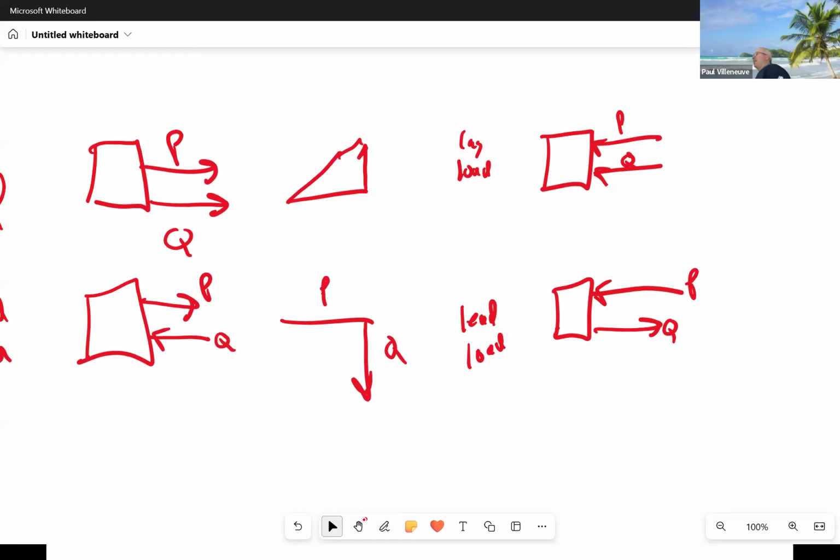So this adds a lot of complication because when we think of load, we think we're always pulling stuff in, but not Q. Q can be in or out. Many, many loads can be providing Q if they're capacitive, right? Remember the ICE part? The ICE part is a leading, because current leads the voltage, in a capacitor. So Q is going to be the opposite direction. So interestingly enough, if I'm a load, if I'm a leading power factor, the Q is actually going out and supporting the grid. If I'm a generator and I'm a leading power factor, I'm sucking Q from the grid. I'm actually pulling Q off the grid.